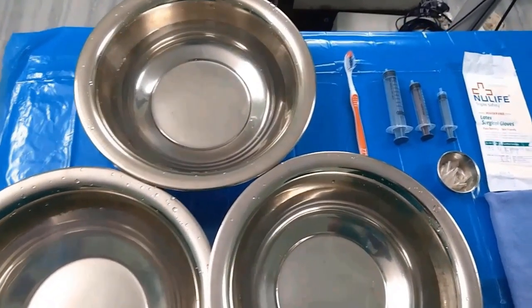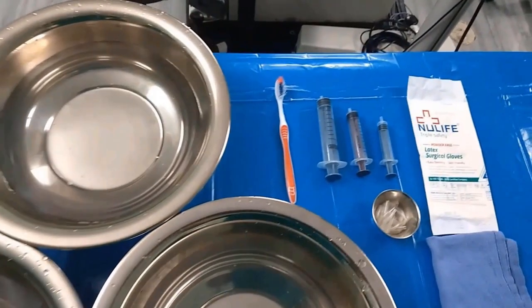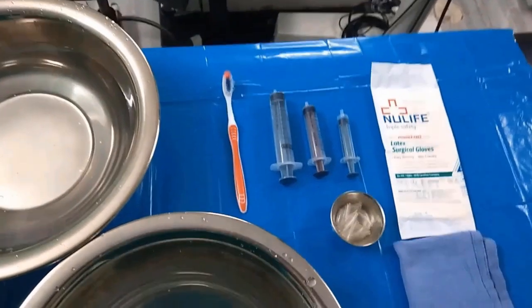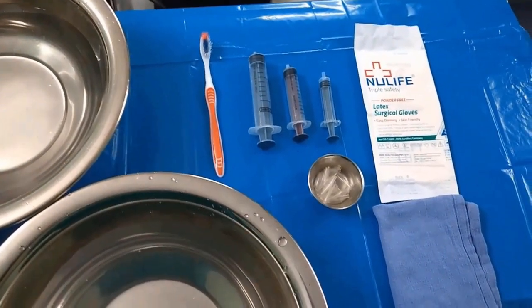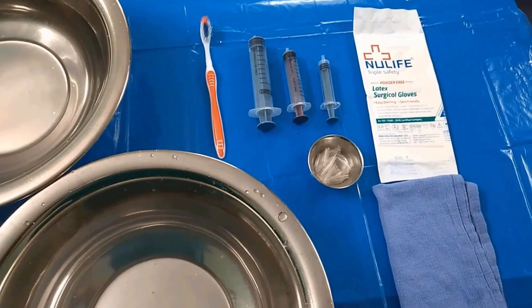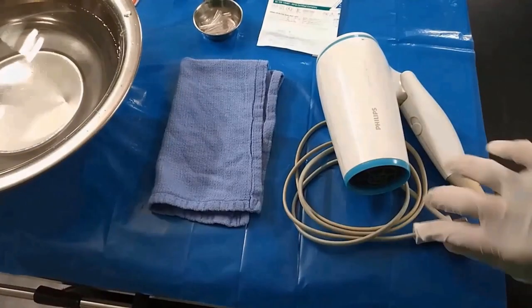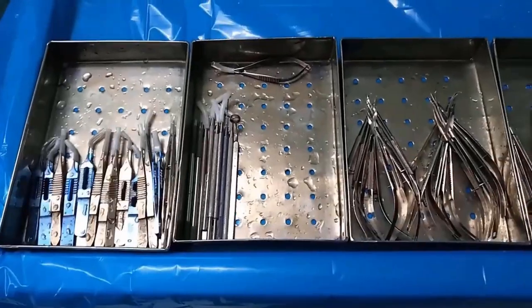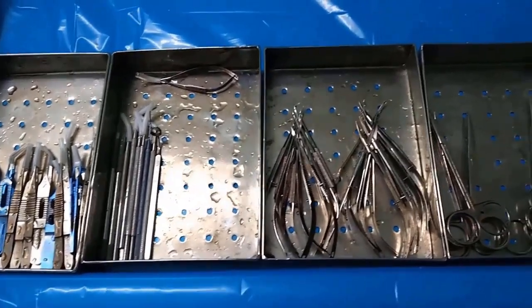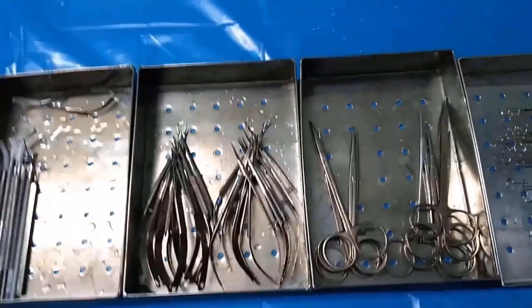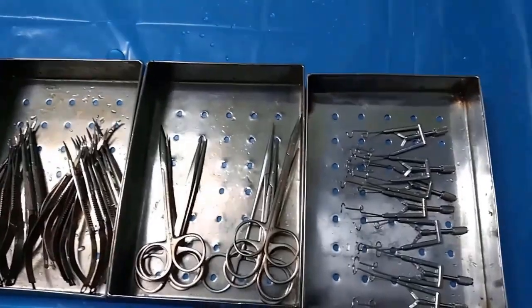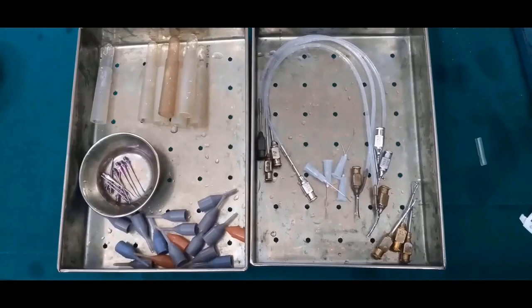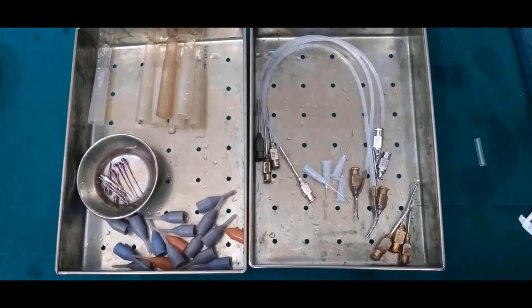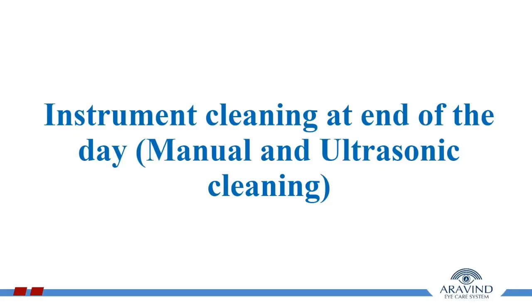Materials required for instruments cleaning are an ultrasonic cleaner, stainless steel basin, filtered RO water, soft toothbrush, 10 ml and 5 ml syringes, hand towel, dryer, tips for sharp instruments and sterile gloves. Before putting instruments in the ultrasonic cleaner, they should be segregated as blunt instruments, sharp instruments, cannulated instruments, needles and phaco tips. Instruments are cleaned at the end of the day by manual and ultrasonic cleaning.